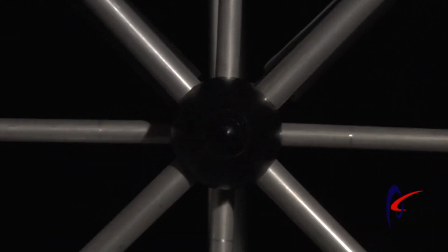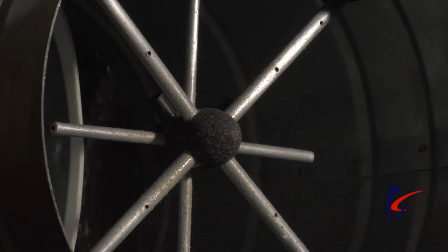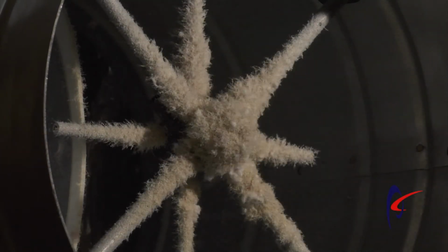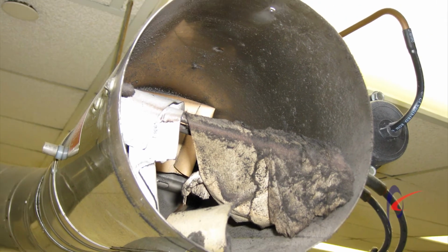When we talk about maintenance, we talk about that cross-flow sensor that sits in the airstream. As air flows past that sensor, the VAV terminal box has to use that as its measurement criteria to decide how much am I going to open or close the blade damper in order to deliver the proper airflow to this space. No matter how much you have good filtration in line with the system, you're going to get some type of particles that are going to accumulate on that cross-flow. They're going to affect the overall measurement ability of that device.